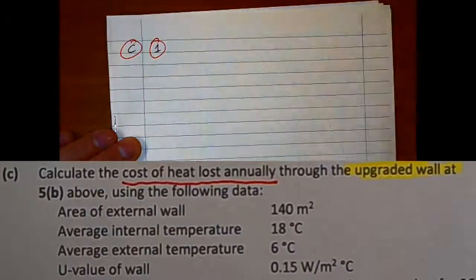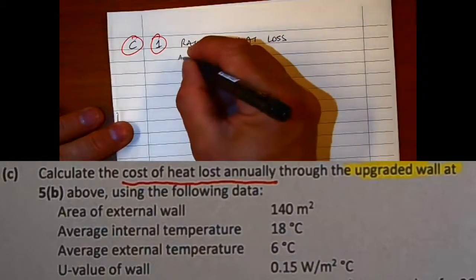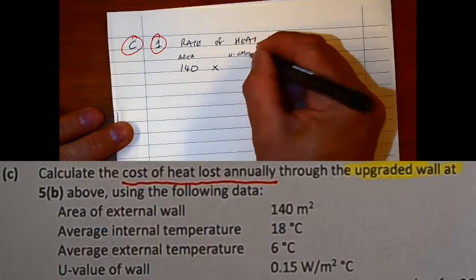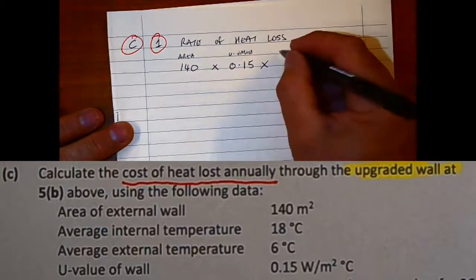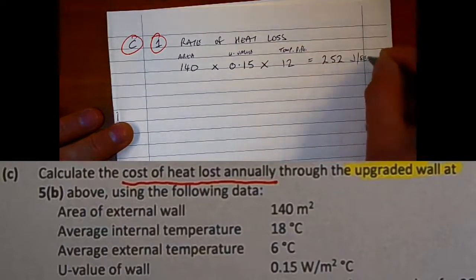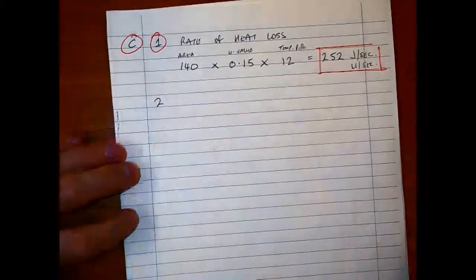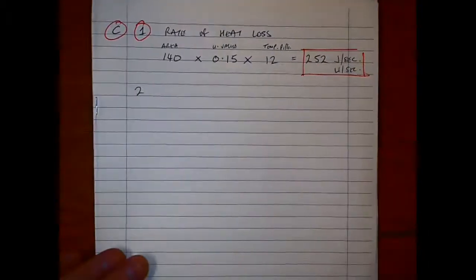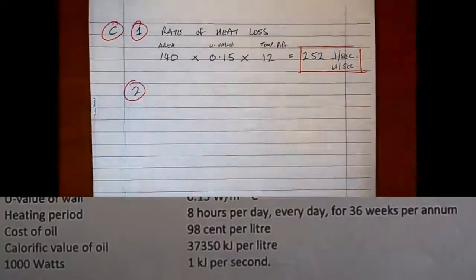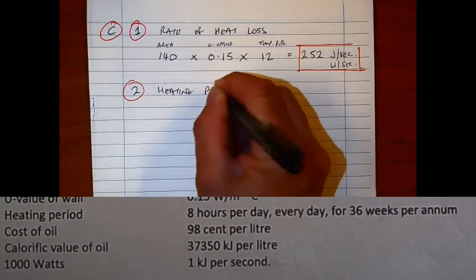For part C of the question, we're asked to calculate the cost of heat lost annually. We're given—and I'm going to break it down into sections here—the very first part we have to work out is the rate of heat loss. The formula for that is: you multiply your area, in this case 140, by the U-value, which is 0.15, by the temperature difference, which is 12 (6 from 18). Multiply that out, and it gives us a value which is measured in joules per second or watts per second, which is important because we break it down into the seconds.